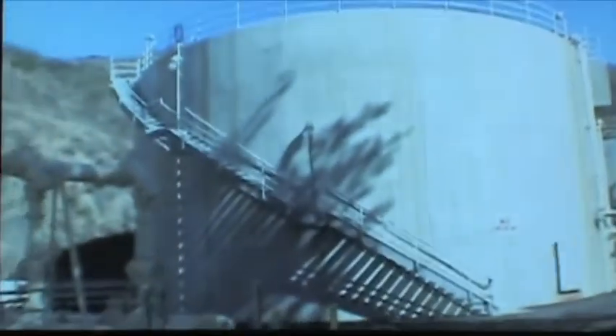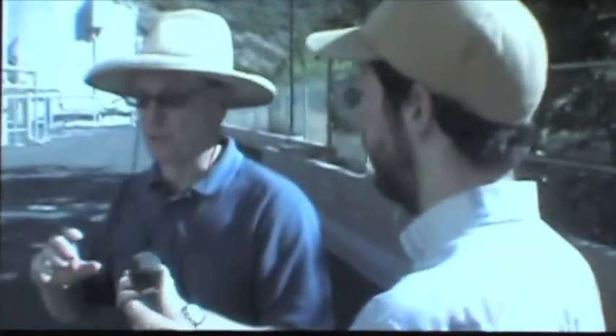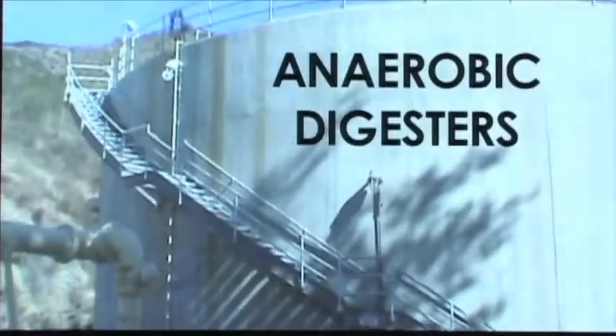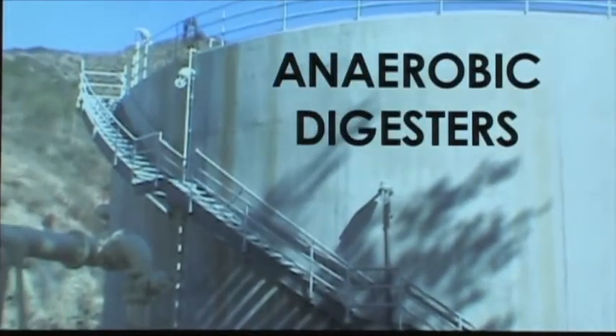Now, if you can imagine, as we're going through the treatment process, I've shown you a couple places where we're removing solids. That solid portion, the waste stream that comes in, ends up over here. The water is essentially what leaves the plant. It's completely free of solids, or we're talking 1, maybe 1.5, 2 parts per million.